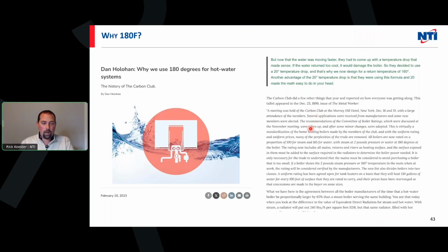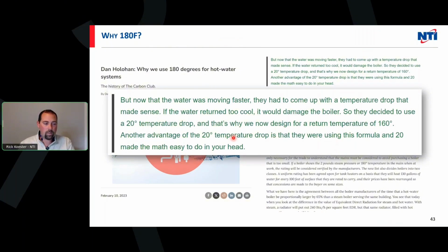Now they did make it kind of a standard for some of the heating emitters that were out there based on heating surface. It had to basically output a certain amount of BTUs per area, based on that 180 degrees that they picked. But as far as the booster pump now and designing something called a 20-degree delta T, something we use for designing circulators now in hydronics. If you ever sat through a Taco presentation, you've heard this before, talking about delta T and temperature drop, right? So they designed this pump around a 20-degree delta T because they were using a formula, and 20 made the math easy to do in their head.